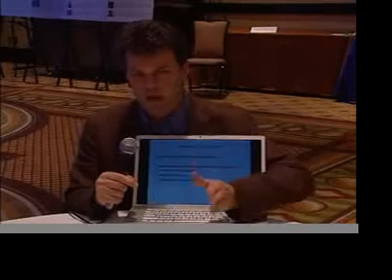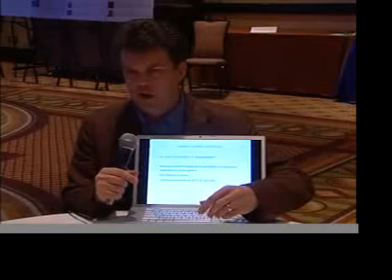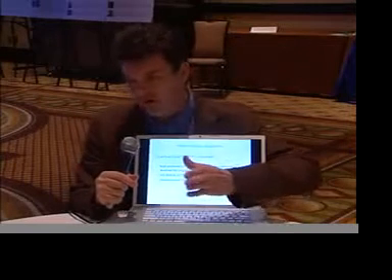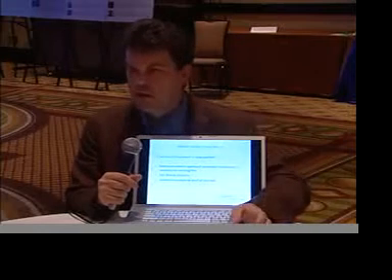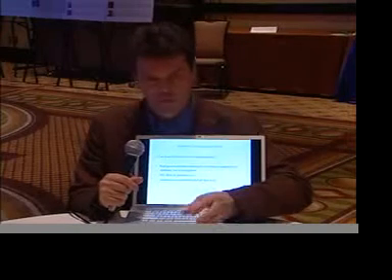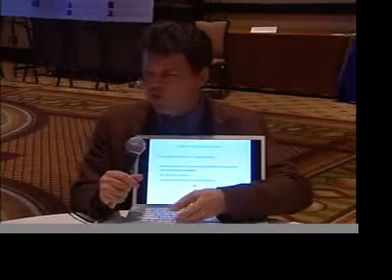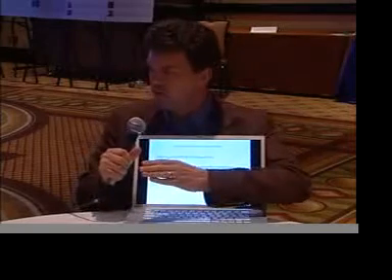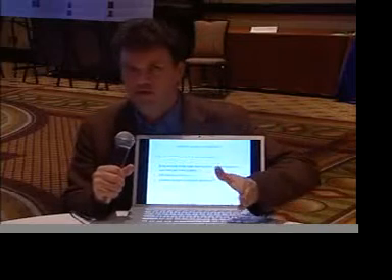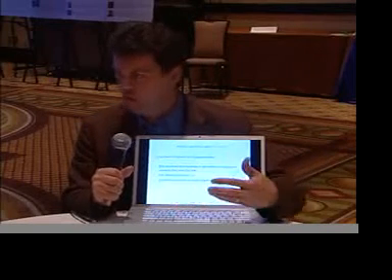And beyond that, if we take it to the other extreme, if we've got blackwater treatment in the basement of a building and we're wanting to reuse that for cooling tower use, well, then we'll have screening, biological treatment, ultrafiltration through membranes, maybe some UV disinfection, perhaps reverse osmosis, chlorine disinfection, because you've got multiple barriers of disinfection, which gives you a higher quality pathogen reduction capability, and therefore you know that it's safe.